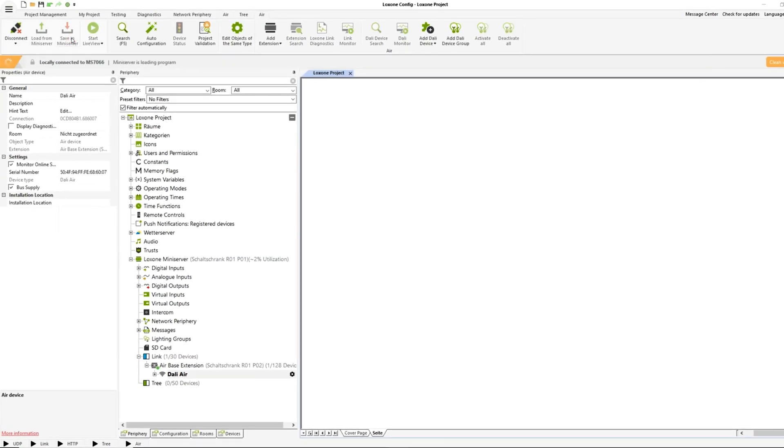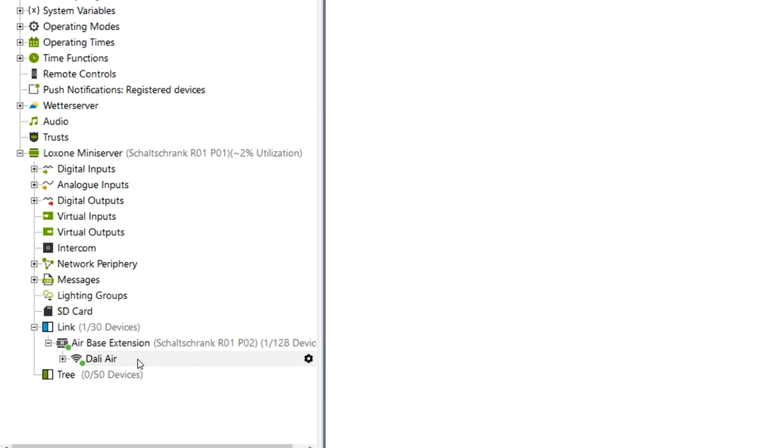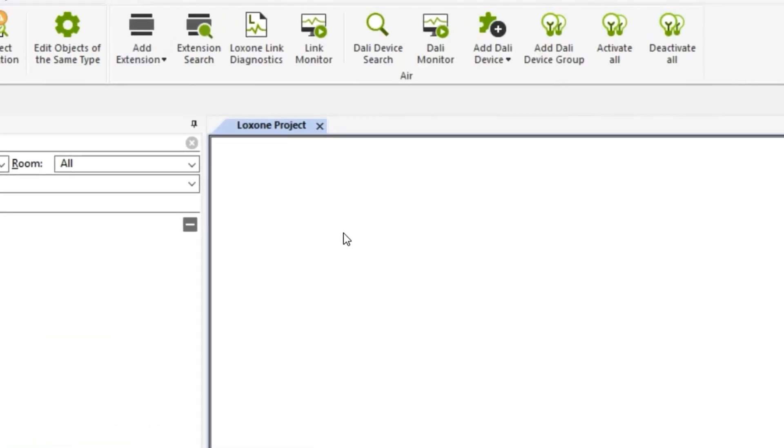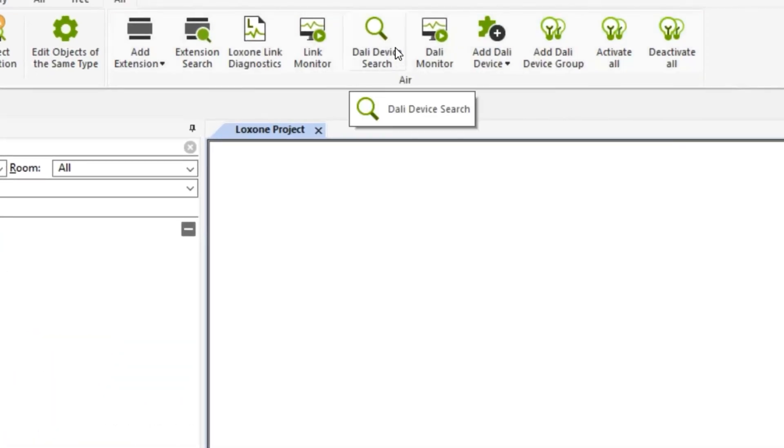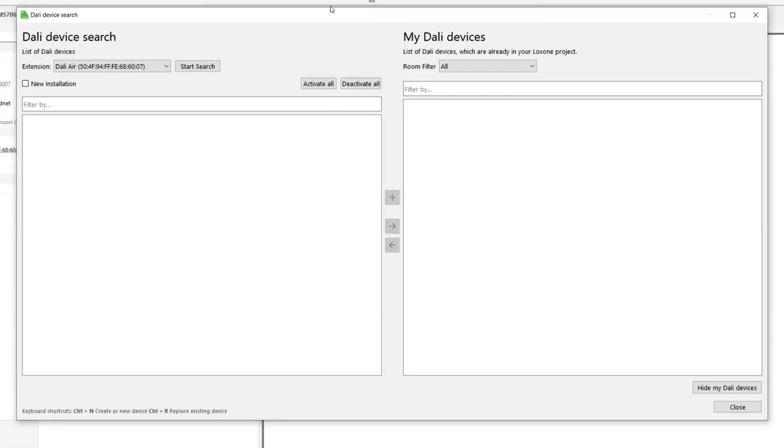Once the DALI Air has been successfully taught in, the DALI search can be started. In a new installation, the complete new installation checkbox must be activated so that all DALI devices are re-addressed during the search. If the DALI extension is installed into an existing DALI installation, a normal search is sufficient to take over all DALI devices and their settings.